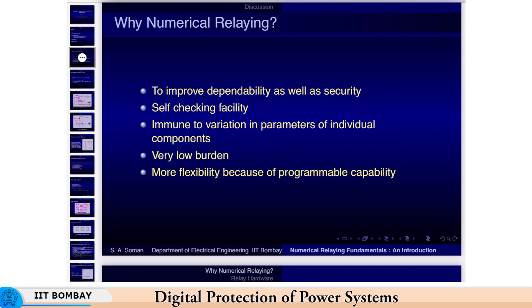Now the flexibility because of programmable capability is something that you have to think for yourself. Otherwise, it's just an implementation of the electromechanical relay. So whatever your innovative thinking is, you could use. For example, earlier if you needed a 3V0 kind of voltage, that is the zero sequence voltage, to implement in some unbalanced voltage scheme, what you would have to do is connect 3 PTs in an open delta formation and get VA plus VB plus VC there, which is nothing but 3V0, and then implement the scheme. Or if you needed the zero sequence current to implement some ground fault kind of scheme, then you actually had to put a CT in the neutral and then calculate the zero sequence current, which was 3I0.